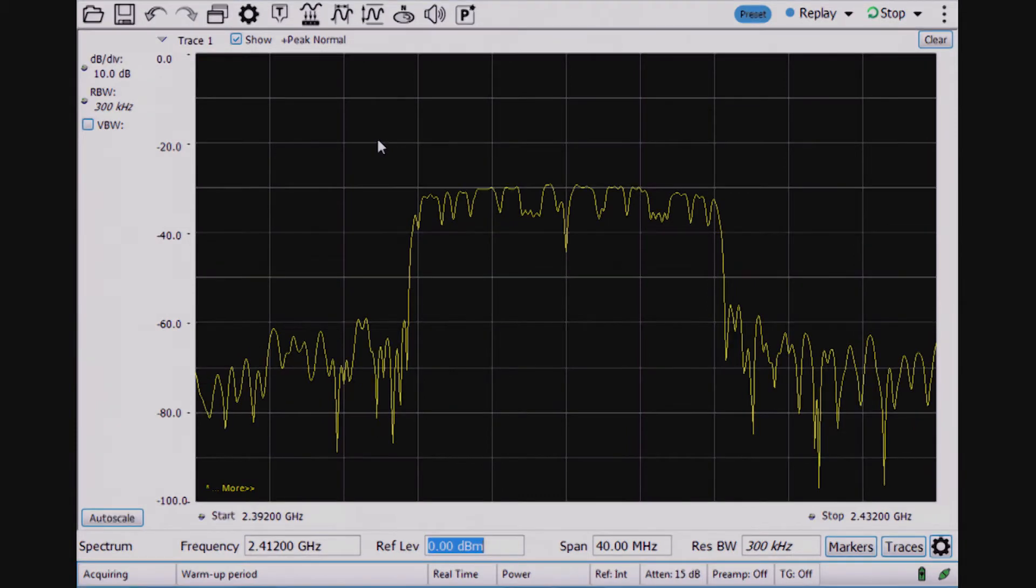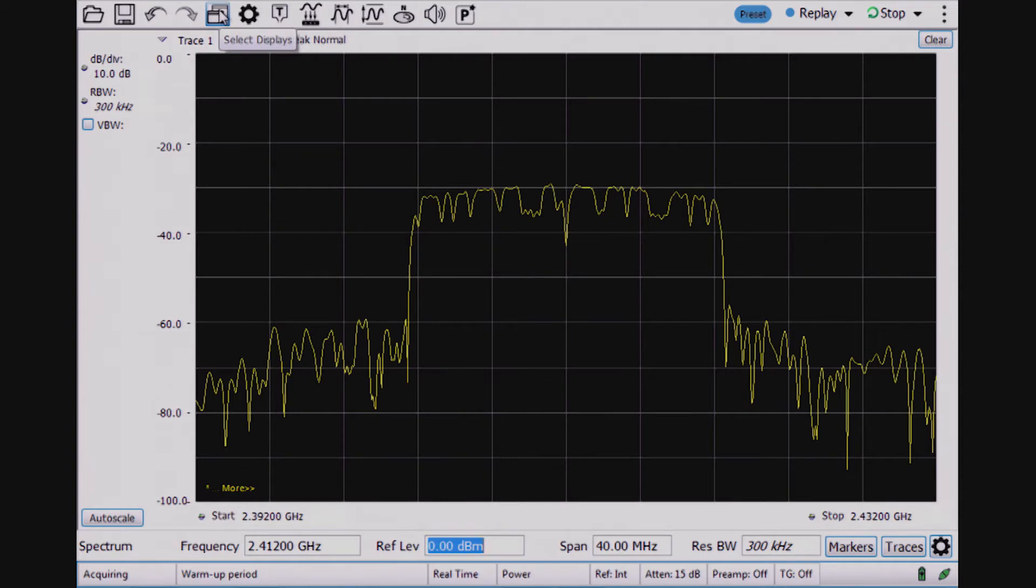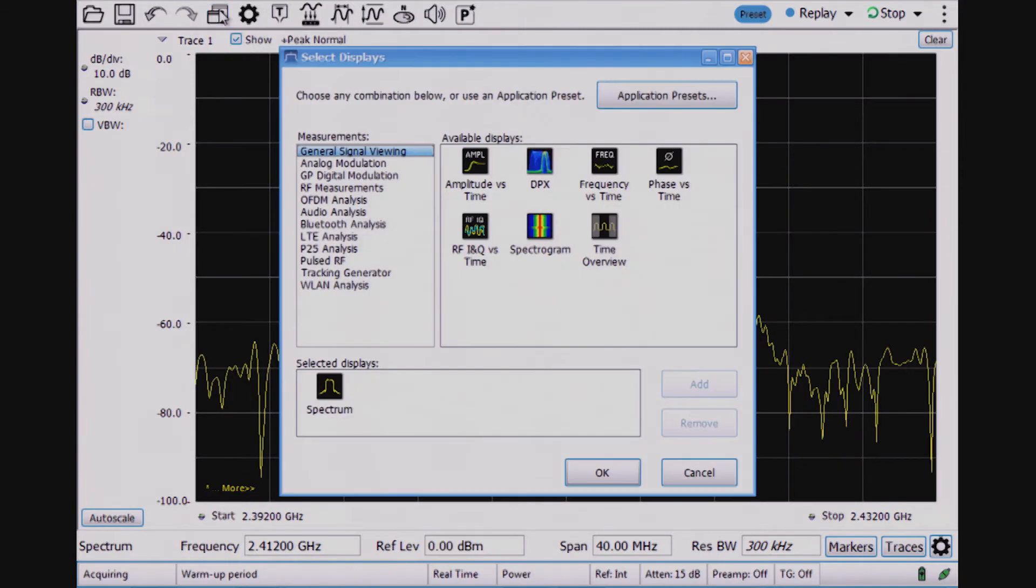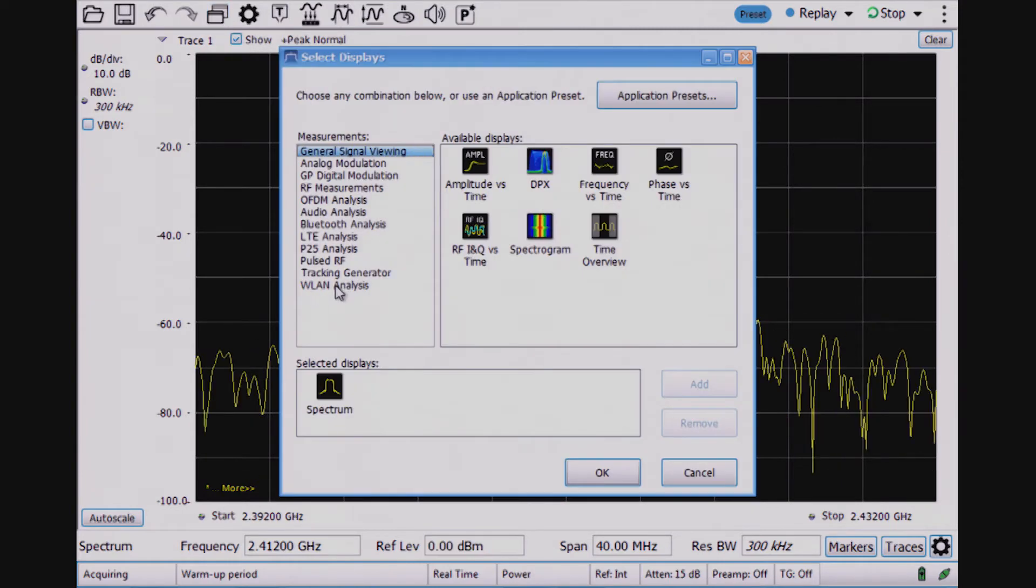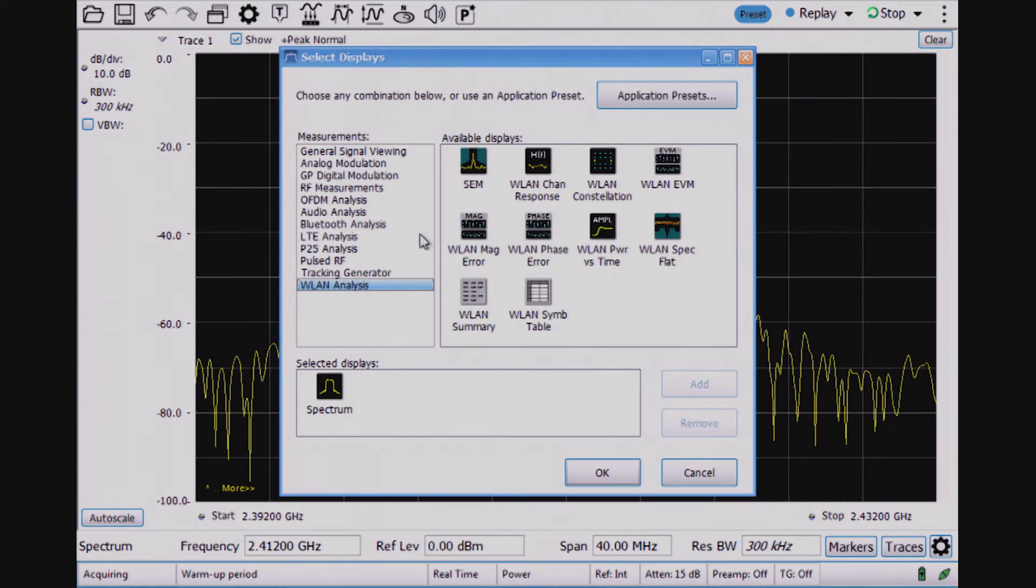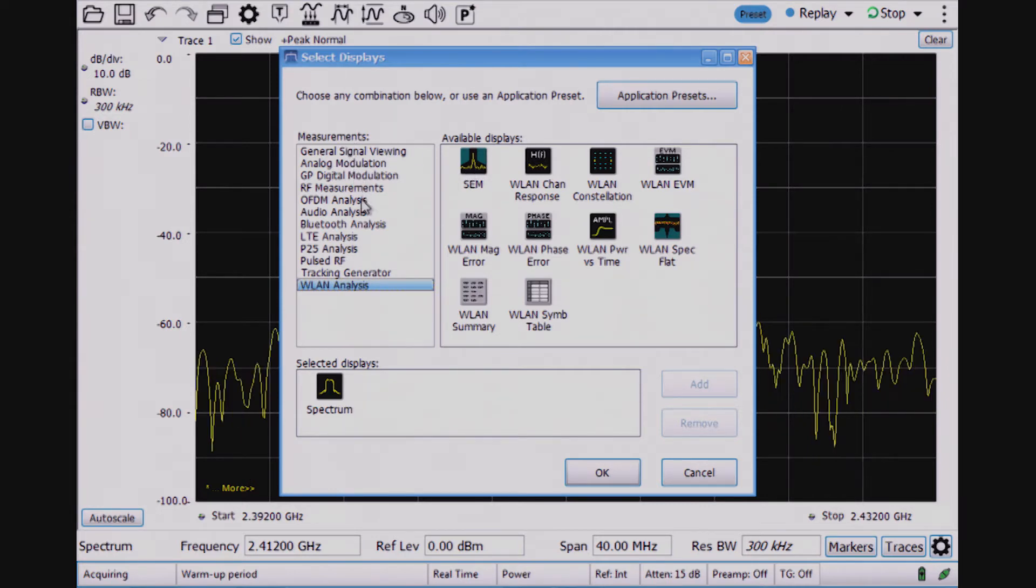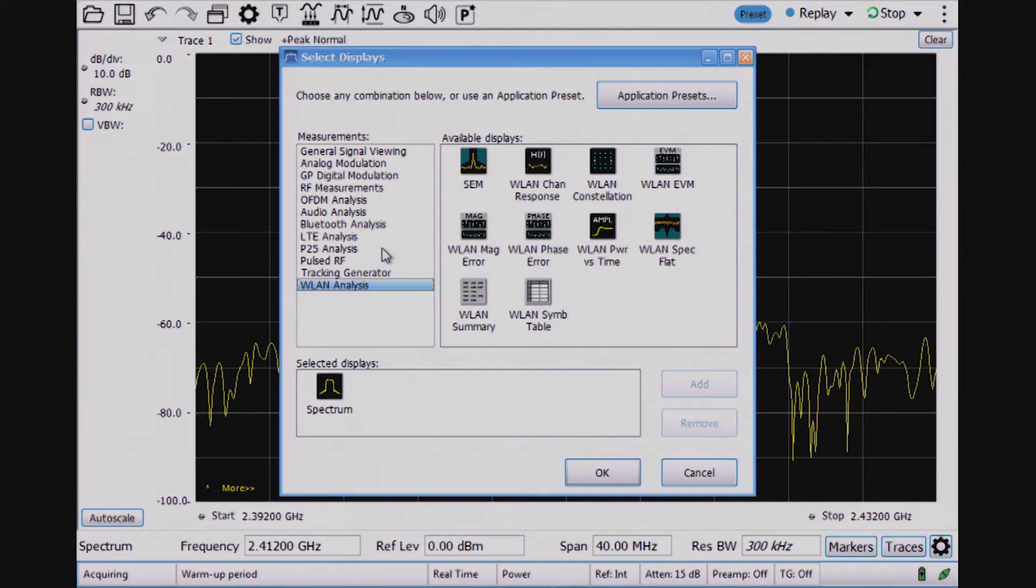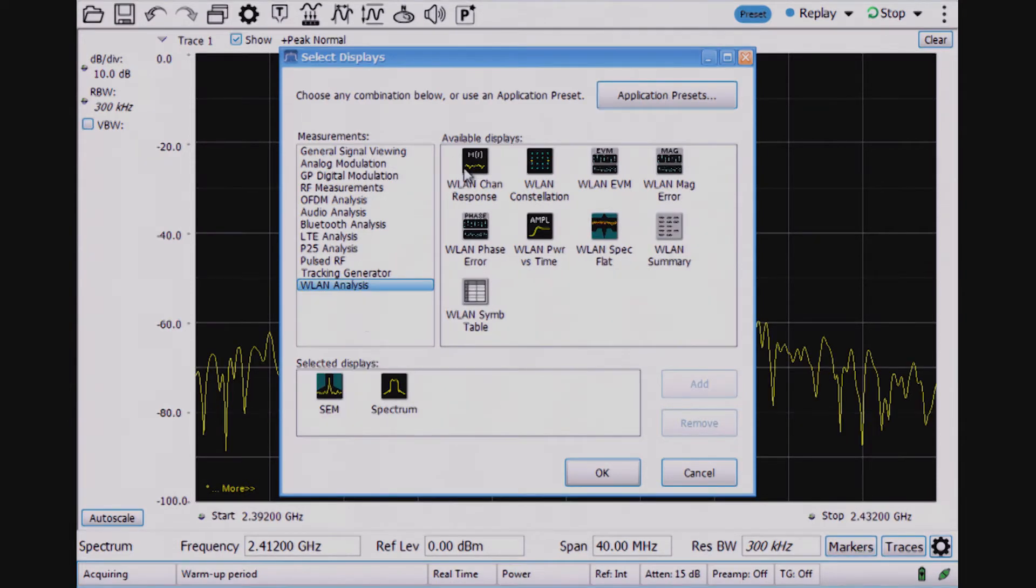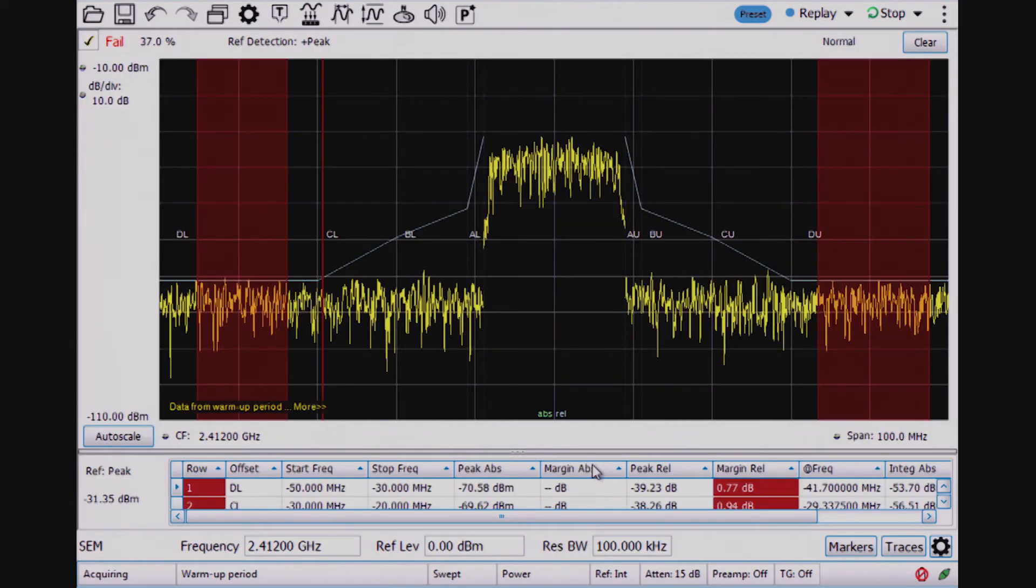For the first check, for looking close into the ISM band, I need to go to the Wireless LAN Analysis Spectrum Emissions Mask. There's a series of folders within the SignalVu-PC software. I find the Spectrum Emissions Mask here, which is already set up for the SEM test.